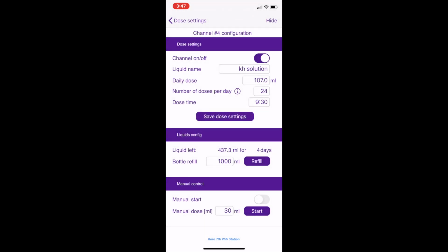Below that, we have the liquid left in the reservoir. Now I've set that my reservoir is 1000 ml, and it's telling me that I have 437 ml left, which is enough for 4 days. If I was to refill it, I just press that refill button. Now when it gets empty, it only turns on the liquid low level alarm, but it won't actually prevent the pump from still running. So if you forget to refill the containers in the app here, but in reality you've actually refilled them, it won't affect the dosing.